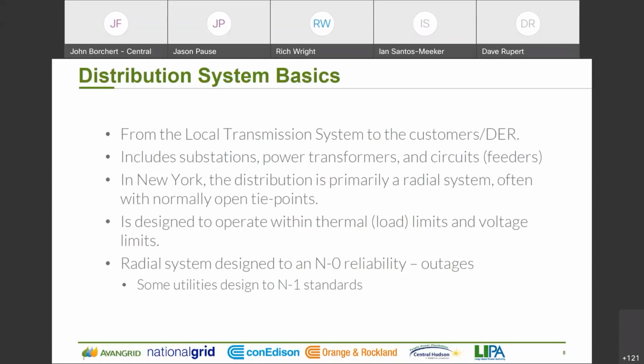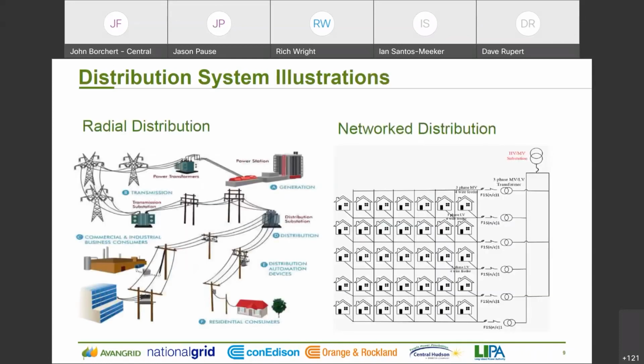Here are two illustrations showing different types of distribution systems. Although the radial distribution system diagram shows the entire system from the generator to the customer as radial, we know that's not the case. The reality is the transmission systems, whether bulk or local, are highly networked systems that operate with redundancy. The radial distribution system is not networked, and while it often has the ability to backfeed through tie points, these are normally open tie points.